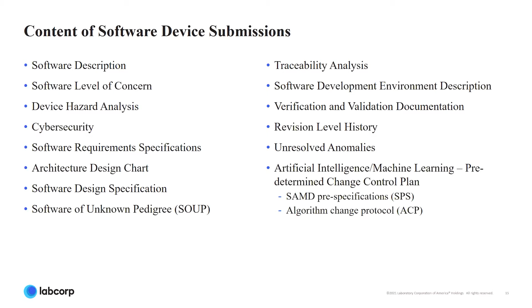Machine learning and artificial intelligence is becoming a bigger and bigger topic. And so there's more and more information out there that FDA has provided on this as well. But this is an area where you'll want to really get buy-in from the agency, from FDA, to really understand how often you would need to submit a new submission. If your software is learning all the time, it's always being updated, you don't want to necessarily have to submit a new submission every time it changes. So there are ways you can set that up ahead of time such that you don't need to submit every time it learns from information being provided.